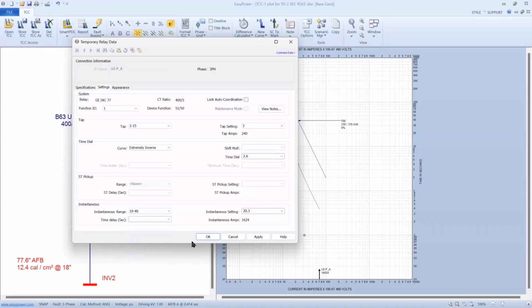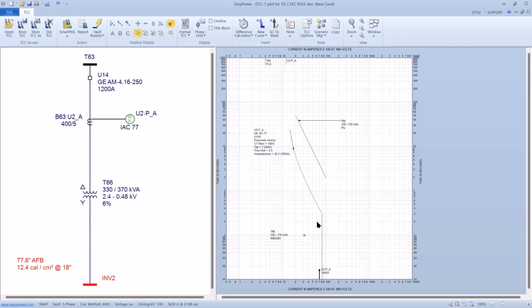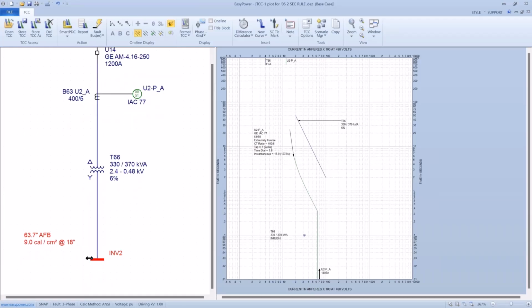So I'm going to put, and so we can see my trip current could be much more reduced or sensitized if I tripped inside of the instantaneous. So now, admittedly, I've taken up a bunch of capacity that could be used, but apparently my loading system isn't taxing my transformer. But now I have much more sensitive instantaneous protection, and I don't have to put on 20 calorie PPE to work on it. Now, whether I want to do that or not, or whether I should do that or not, has a lot to do with what's going on down here. But we show it as just a bulk load. And so questions should be asked before you do something like that.